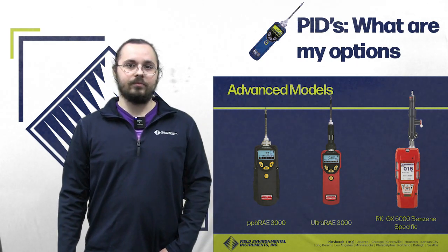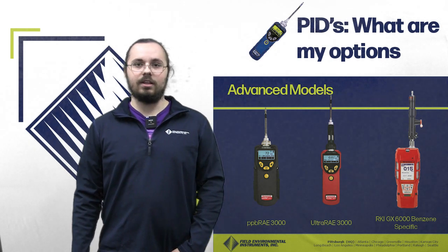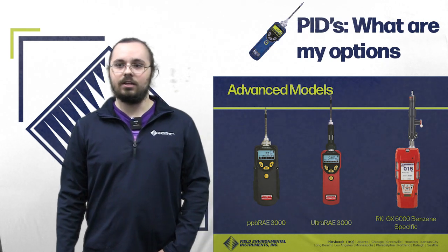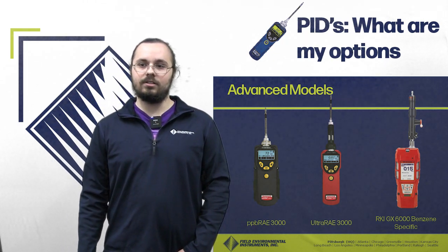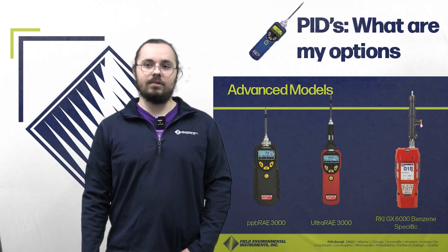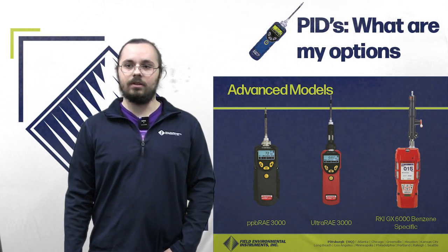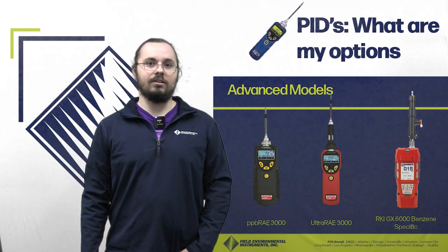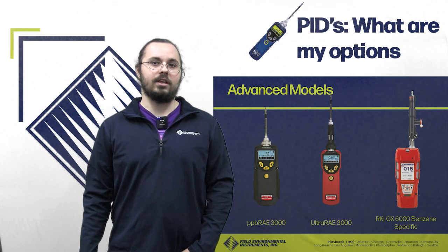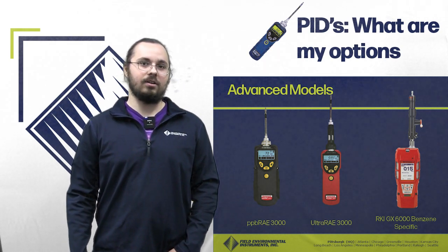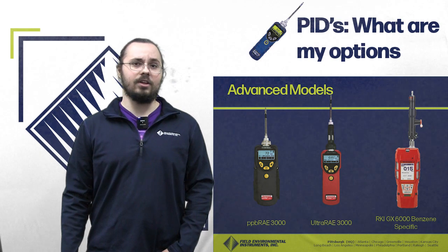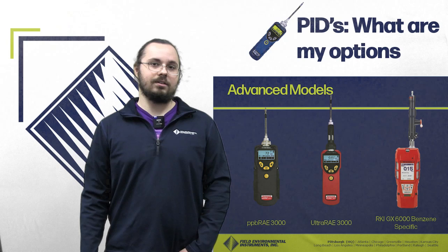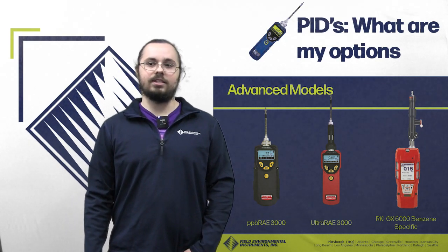The UltraRAE is very similar to the MiniRAE as well, except in this case it's mainly used for benzene applications. Its PID extended range of VOCs is from 0 to 99.99 ppm, and it has a benzene-specific tube you can install in it, which allows it to filter out all other compounds except benzene, giving you accurate benzene readings.